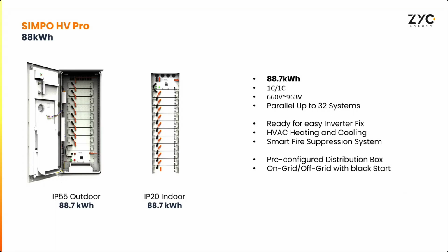Auto-commissioning means you install it on site, put the battery modules in, connect them easily with the fast connectors together into one system, switch it on, and that's it. It's not needed to do any commissioning on the system because it does it by itself. So the BMS in the PDU is doing all the commissioning and also recognizing the number of modules and the communication to the inverter. Everything is fully automated, and I think that's one of the great highlights of our product.